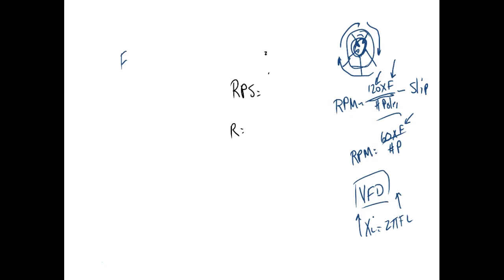So what we have to do is increase the voltage. So a variable speed AC motor, if we raise the frequency, we raise the voltage. If we lower the frequency, we lower the voltage, right? You understand that? So they're basically variable speed drives is what they are. So AC speed drives have to control 2 things. They have to control what? Voltage and frequency. So we're not using the voltage to change the speed. We're using the voltage to keep the torque of the motor constant. Because if I raise nothing but the frequency, the motor would lose torque. If I lowered the frequency, the motor would pull more current and try to create more torque, right?